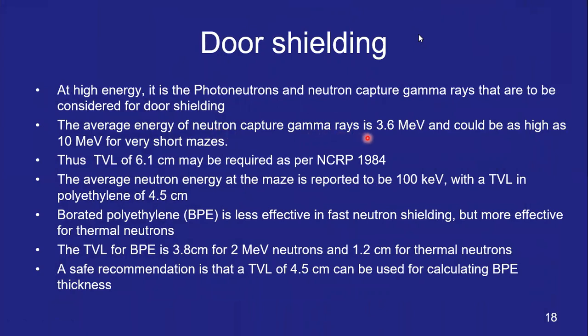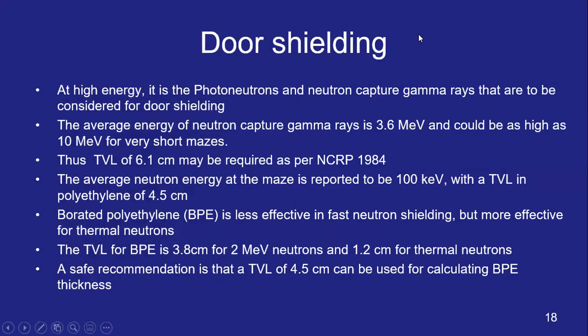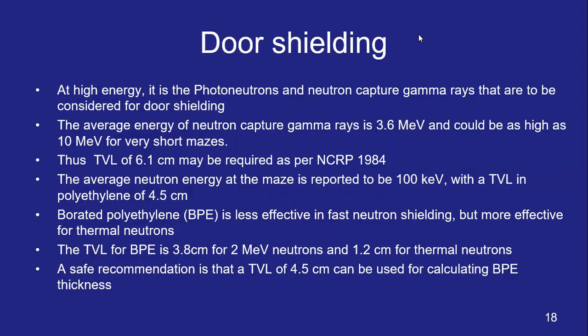At high energy, door shielding must consider photoneutrons and neutron capture gamma rays. The average energy of neutron capture gamma rays is 3.6 MeV and can go as high as 10 MeV for very short mazes. A TVL of 6.1 centimeters of lead may be required per NCRP 1984. The average neutron energy at the maze is about 100 keV with a TVL in polythene of 4.5 centimeters. Borated polythene is less effective for fast neutrons but more effective for thermal neutrons. The TVL for borated polythene is about 3.8 centimeters for 2 MeV neutrons and 1.2 centimeters for thermal neutrons, so 4.5 centimeters is a safe recommendation for calculating BPE thickness.